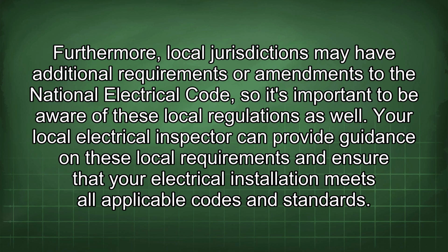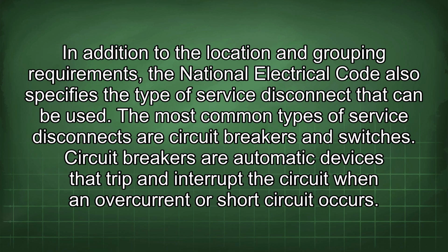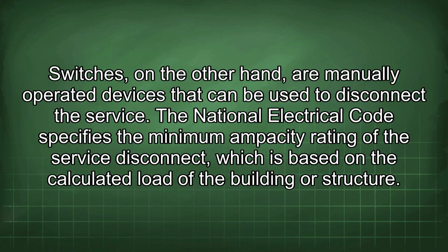codes and standards. In addition to the location and grouping requirements, the National Electrical Code also specifies the type of service disconnect that can be used. The most common types of service disconnects are circuit breakers and switches. Circuit breakers are automatic devices that trip and interrupt the circuit when an overcurrent or short circuit occurs. Switches, on the other hand, are manually operated devices that can be used to disconnect the service.